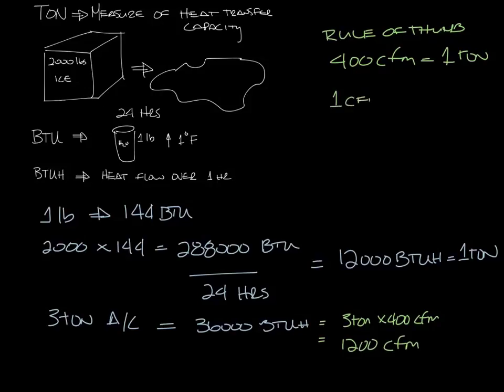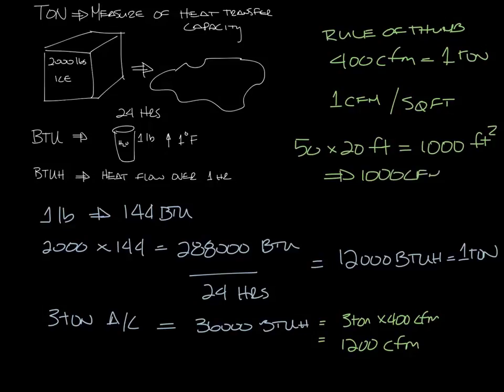Another rule of thumb is that you have about 1 CFM per square foot. So you can use this if you know the size of a space. So maybe you have a space that's like 50 foot by 20 foot. So 50 times 20 is a thousand square feet. So now you take your thousand CFM, because it's 1 CFM per square foot, divide that by your 400 CFM a ton, and that comes out to about a two and a half ton unit. And if you multiply that by 12,000 BTU a ton, you'd get 30,000 BTU.